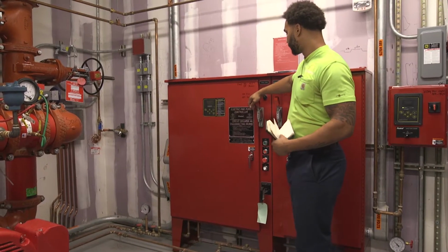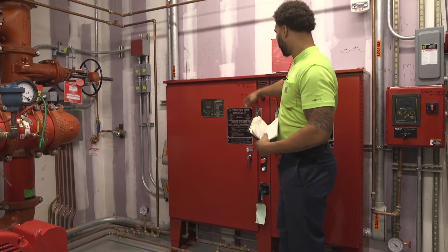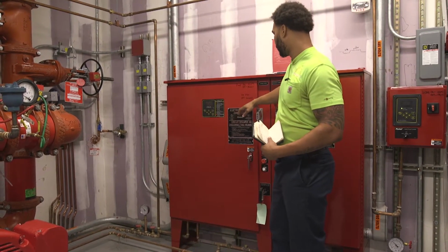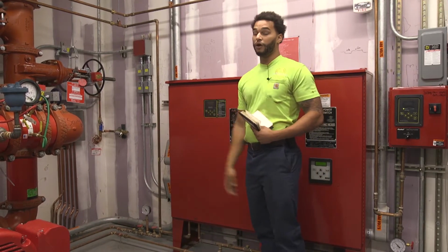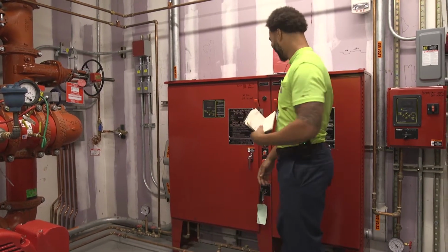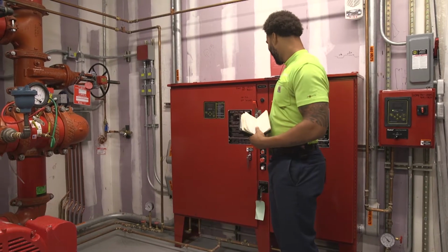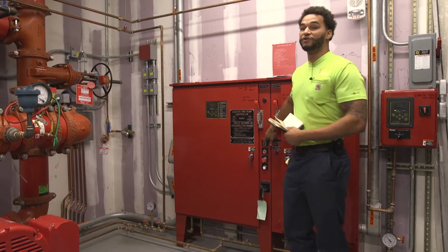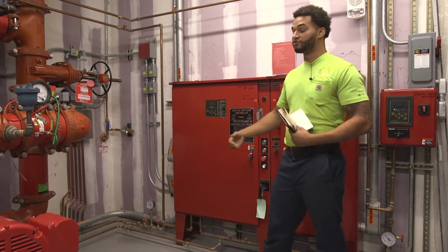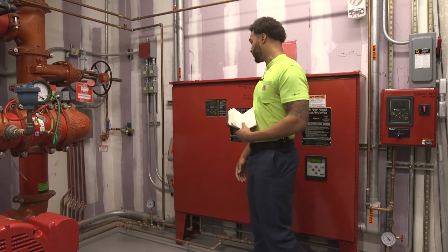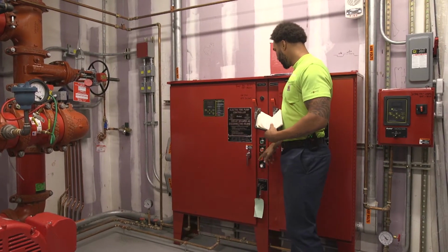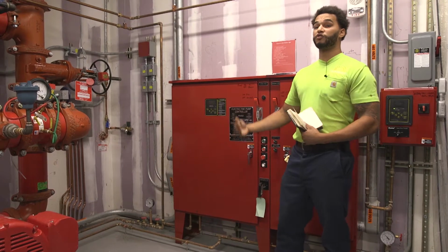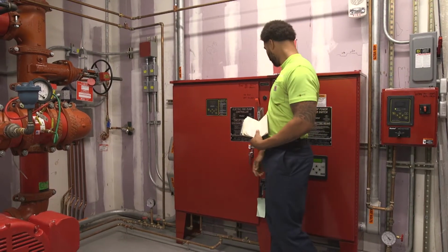Here we have our circuit disconnect switch. Killing this switch is going to kill power going into our breaker that feeds the motor with energy and makes the motor run. Here we have our start button. You push this button one time and it's going to slowly start the fire pump up and bring it up to full speed. Here's the stop button. We push this button one time and it's going to slowly stop the pump down.